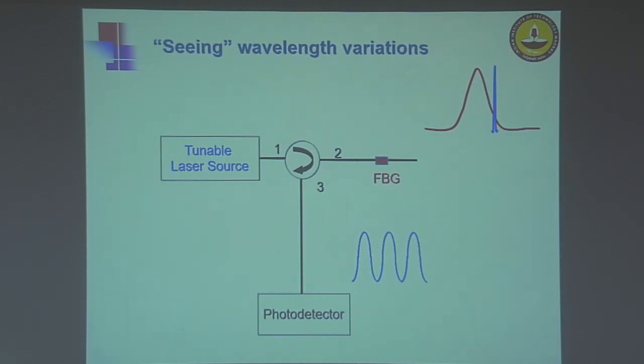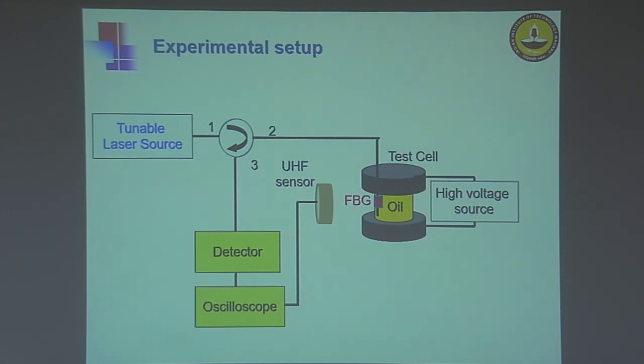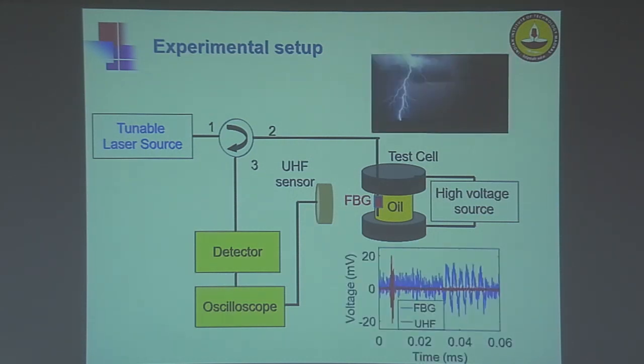We went ahead and tested this technique at the laboratory level to detect partial discharges. I have the experimental setup here, where I use an oil-filled miniaturized test cell which has the facility to generate a discharge when excited by an appropriate high-voltage source, and I paste my fiber Bragg grating sensor on the inner surface of the test cell wall. The grating is interrogated with the help of a tunable laser, and in addition, we use an ultra-high frequency sensor to capture the electromagnetic pulse emitted by the discharge, which serves as a reference measurement. A typical time-domain trace captured in this experiment shows the signal in red captured by the UHF sensor and the signal in blue as the acoustic wave captured by the FBG sensor.